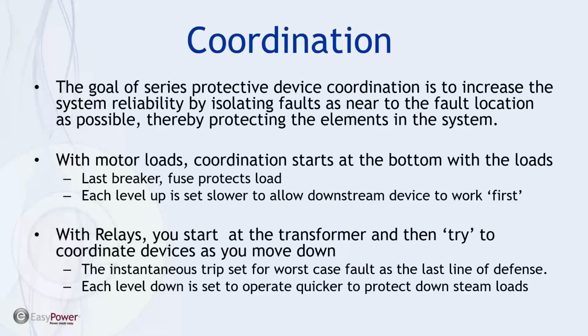The goal of coordination is not a requirement for any part of the system legally, except for emergency and critical mission systems. And it's advised, though, to increase the reliability and dependability of the system by being able to allow the protective devices to trip as close to the fault as possible.